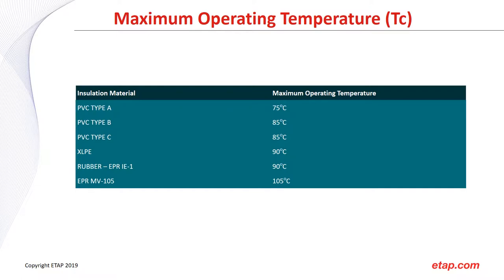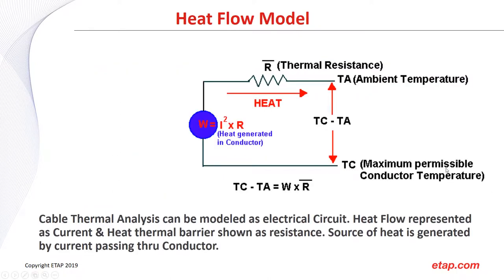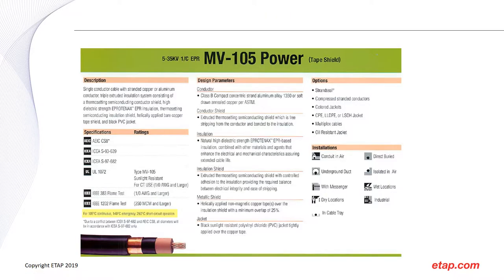The maximum operating temperature is the TC value — the maximum permissible conductor temperature. Depending on the insulation material of your cable, you'll have a different maximum operating temperature. For example, PVC Type A insulation has a maximum operating temperature of 75°C, while an EPR medium voltage cable has a maximum operating temperature of 105°C. The insulation material has a direct impact on the maximum temperature.